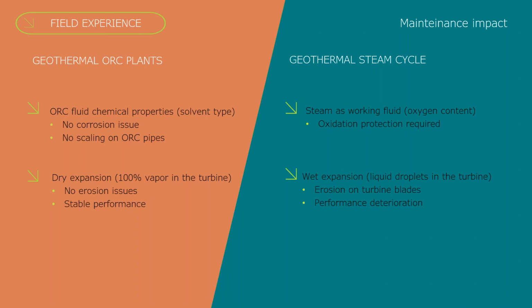The other key difference between the steam cycle and the ORC is related to the thermodynamics of the expansion of the working fluid in the turbine. While in the steam cycle the water during the expansion goes into the two-phase region, it means that there is the formation of liquid droplets in the turbine, which impact on the turbine blades, causing erosion, and therefore the performance gets worsened along the plant operation because of the erosion of turbine blades.